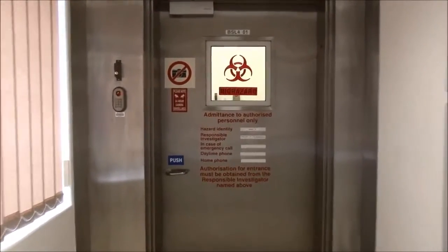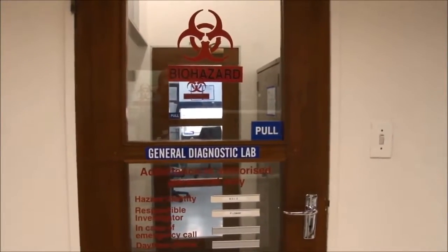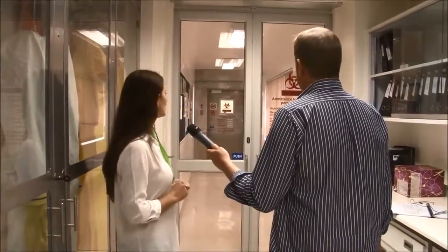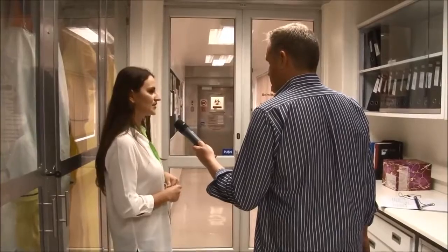It's airtight according to certain criteria. In regular labs over here we just do administration and work with rabies and things like that. But if you go through here, the doors are actually double interlocked doors with a gasket seal, so the lab is completely sealed off. If you want to go into the lab, you deflate one door, go into the cubicle, close the door behind you, and then the next door will open. So it's a complicated affair to get into the lab. And obviously, to get in, you'll have to wear one of these suits.